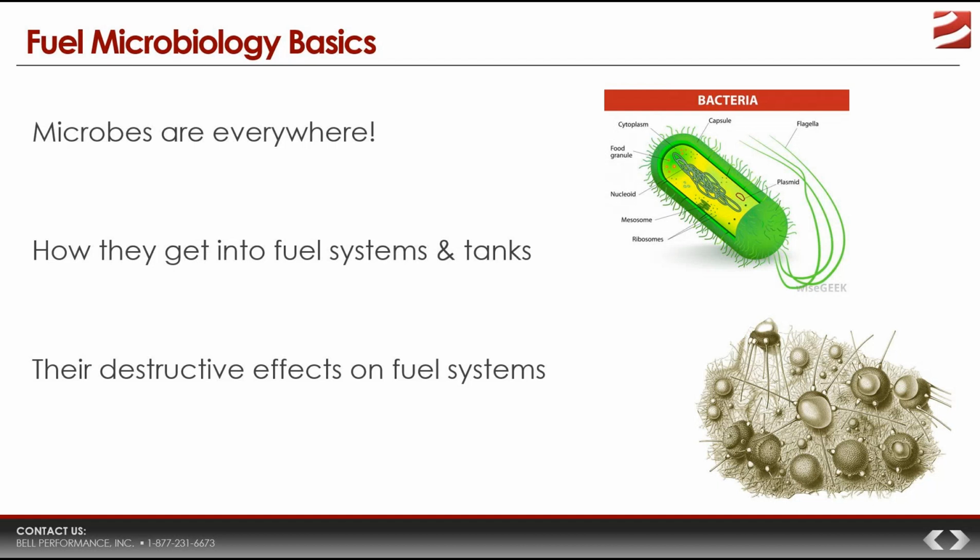Now, if you take one single, what they call a planktonic microbe that's in the liquid fuel, it only takes 24 to 48 hours for one single planktonic microbe to establish itself on a solid surface and form a viable, complex microbial colony. And in any given storage tank that has a biofilm presence already in it, you're likely to find thousands of different species of microbes, all requiring differing levels of different kinds of things to grow, all depending on each other, living kind of symbiotically to live life to the fullest and do what they want to do.